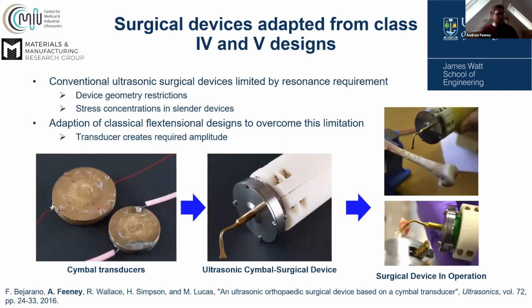The next part of my work looked at adapting class 4 and 5 designs for fabricating surgical devices. Now, conventional surgical devices tend to be limited by resonance requirement, so that affects Langevin transducers in particular. So that's why I moved to using Flextensional based designs. For a Langevin stack transducer, every part of it has to be precisely tuned, whereas with a Flextensional, we're able to attach a cutting insert onto the top without precisely tuning it to the resonance of the device, purely because it's operating in a flextensional motion. So the vibration of that membrane, for example, in the picture you can see in the center, that's just a completely different operating mechanism to a stack transducer.